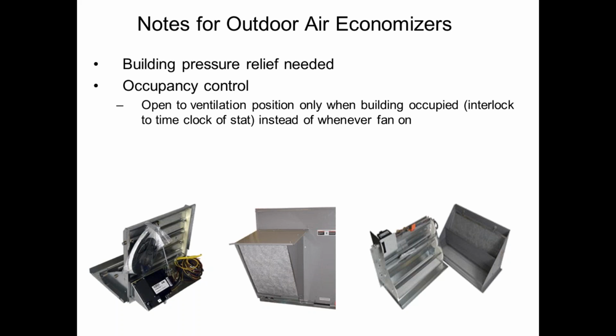I also have to think about both logic and the code. So a normal package rooftop, every rooftop unit you've specified, installed, or serviced in your whole entire life probably, except for DDC ones, but all the regular non-DDC units, whenever the fan turns on, the economizer automatically goes to minimum ventilation position. It doesn't matter if it's in the middle of the night. It doesn't matter why the fan turned on. As soon as the fan turns on, we open up the damper for ventilation. So that means unoccupied times in the middle of the night, we get a heating call so the building doesn't freeze or whatever. We start ventilating with outside air for a building that has no people.